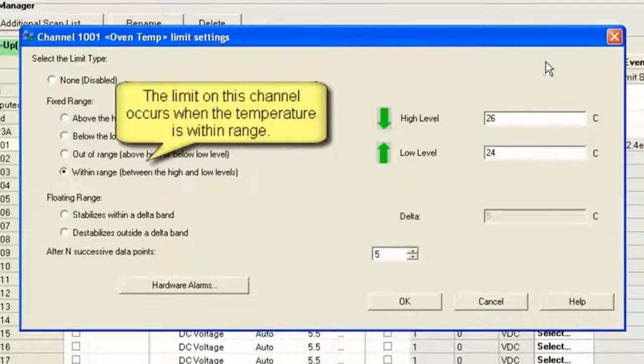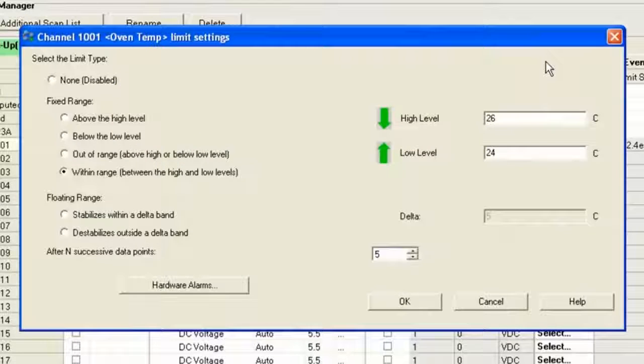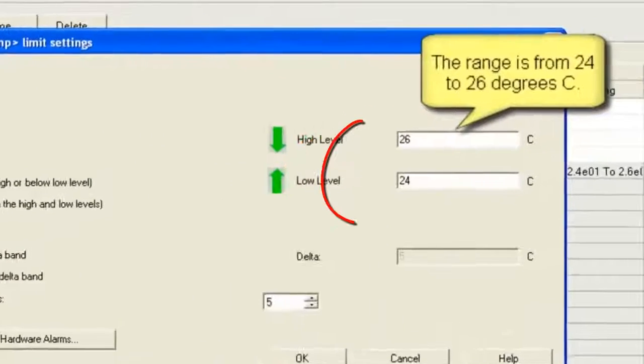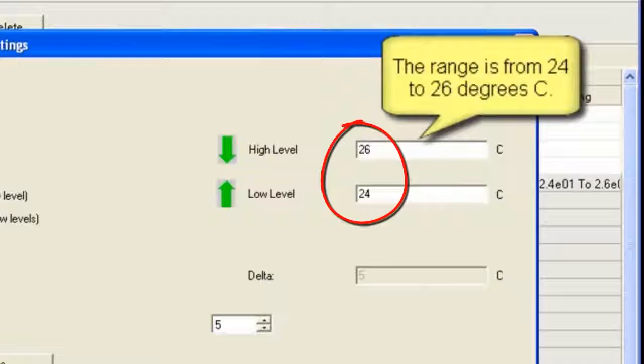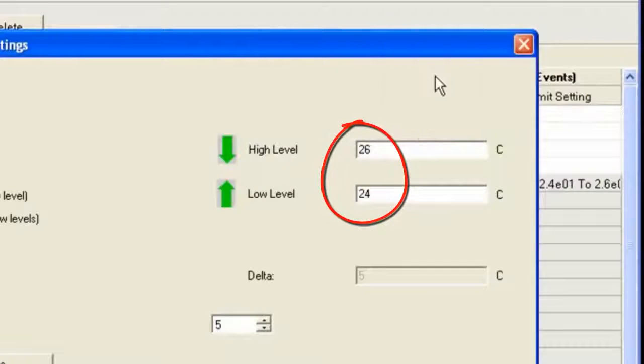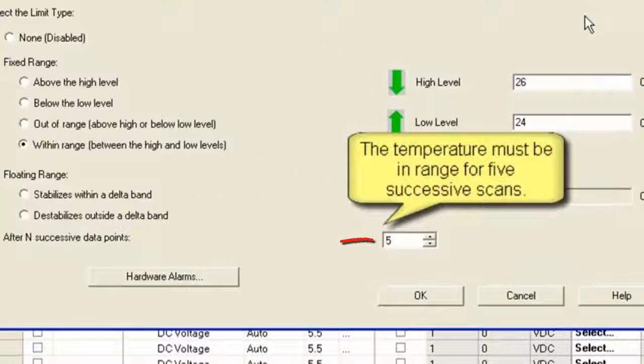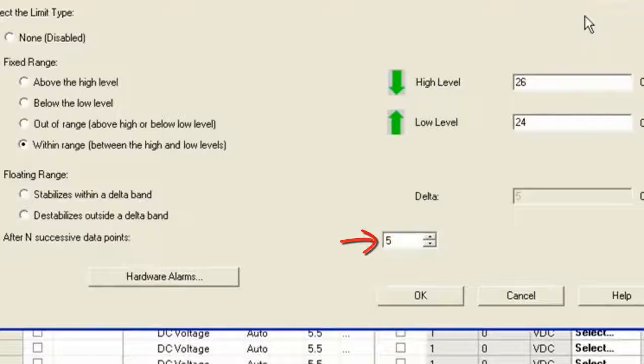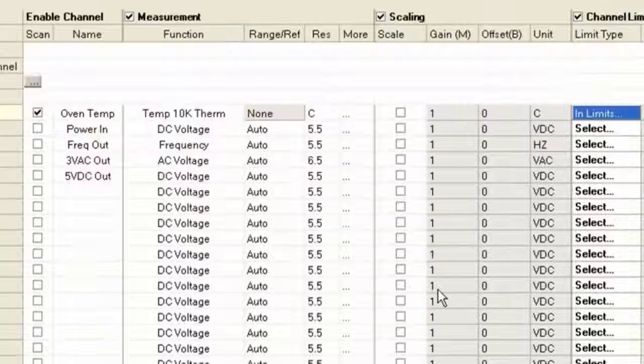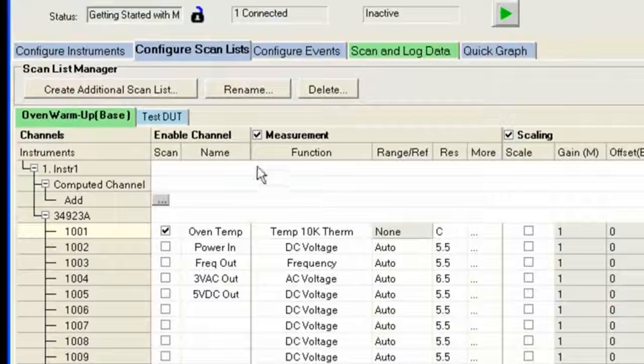Now we want to look at limits within the temperature, so I've set up two different high-level and low-level temperatures. It's got to be between 24 and 26 degrees C, and I'm going to look at that until I see it within those limits for five different scans to make sure the oven temperature has evened out and stabilized.